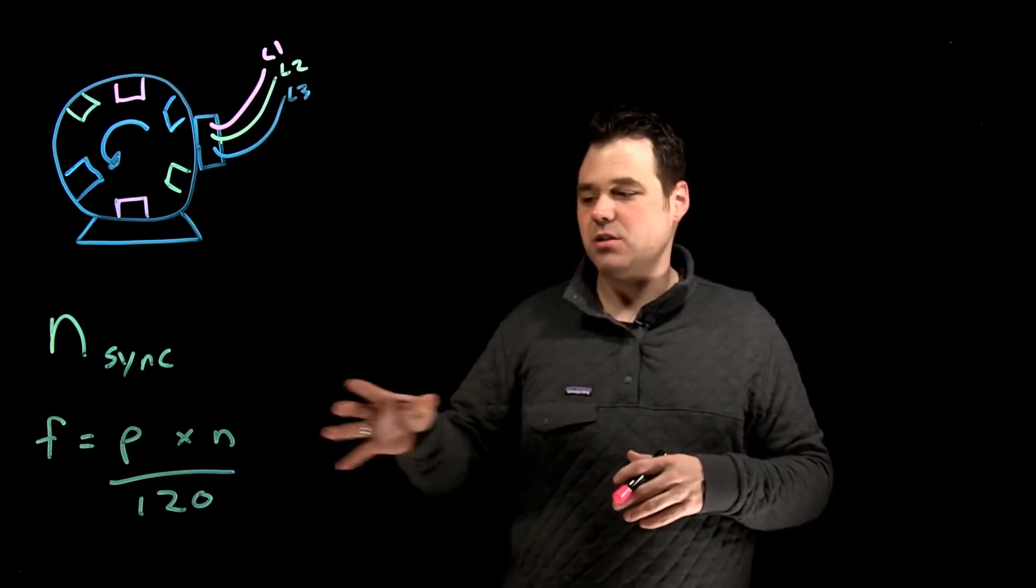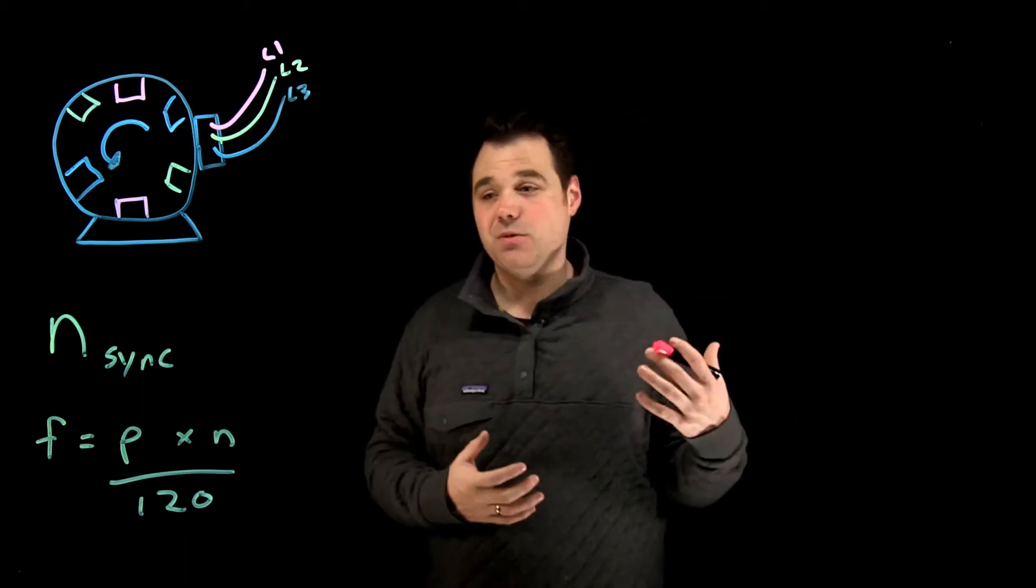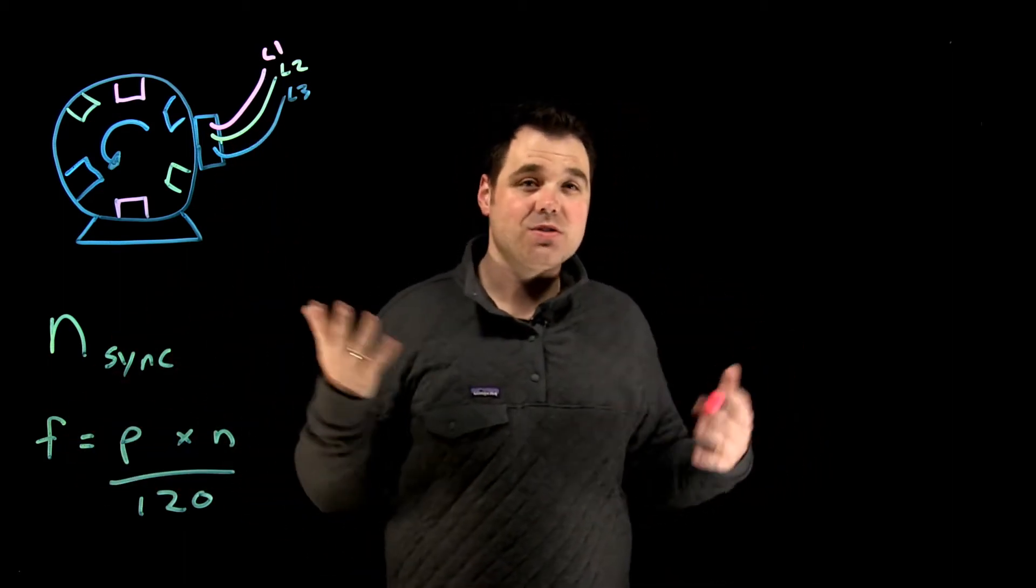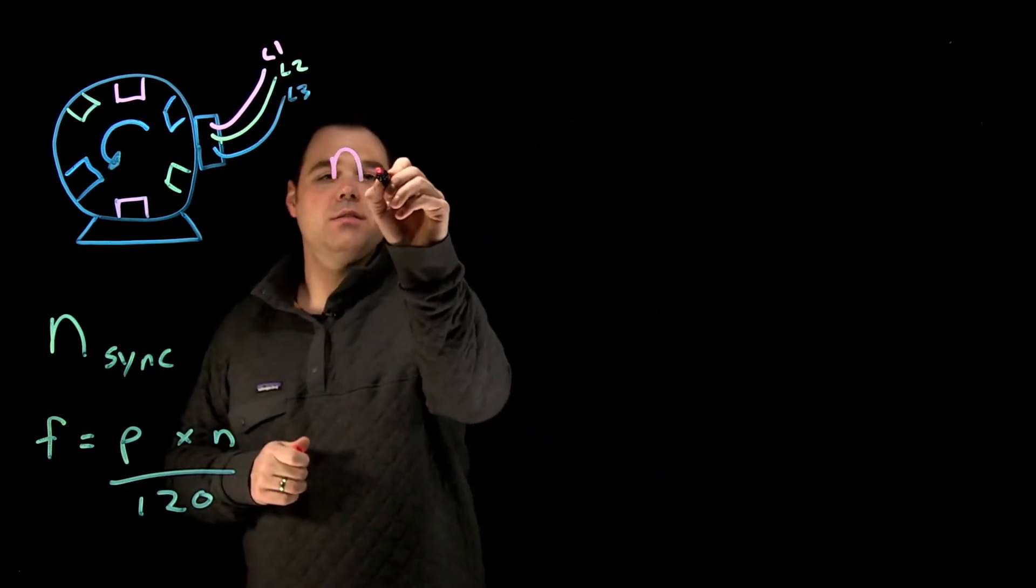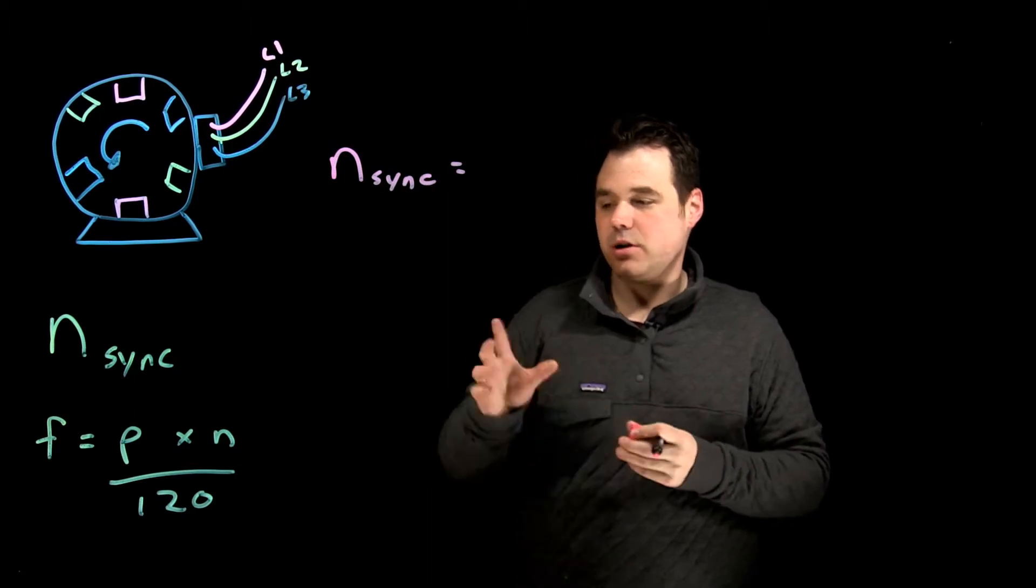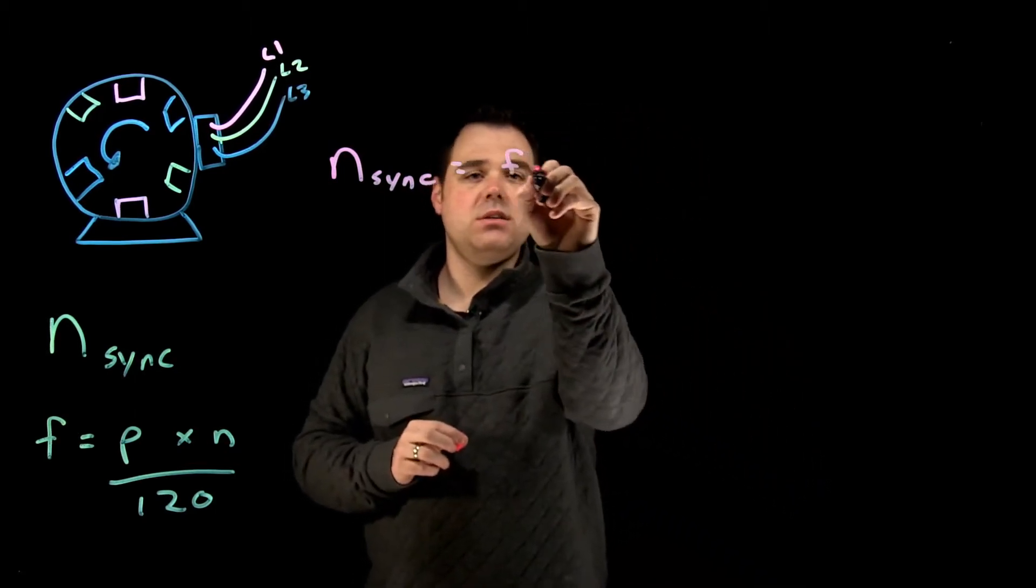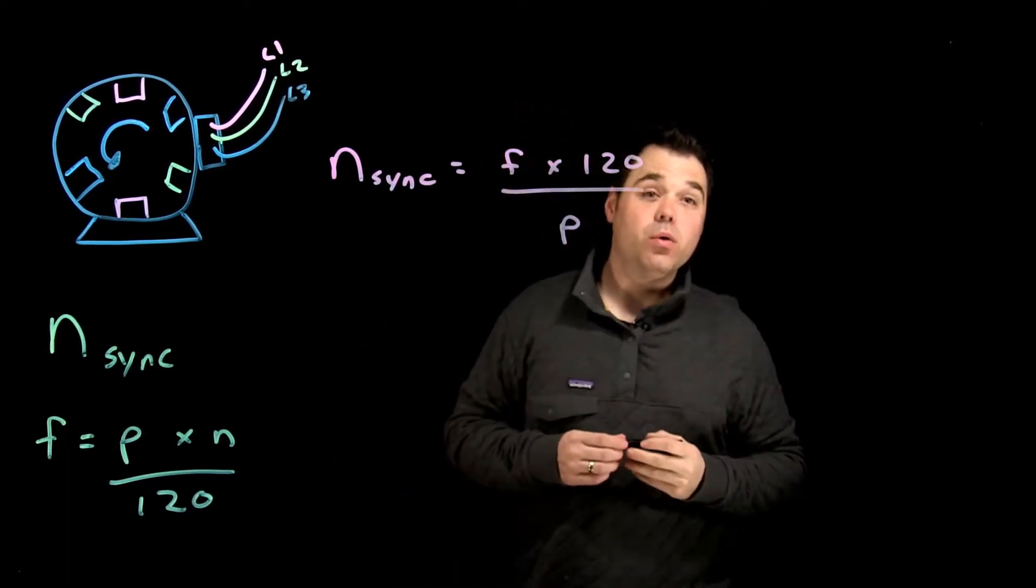Now what we're talking about is we're going to use this same formula, only we're going to transpose it. We're going to have a set frequency because we're connected to a source, so we're going to talk about 60 hertz. So we're going to take that formula—n sync equals frequency times 120 divided by the number of poles.